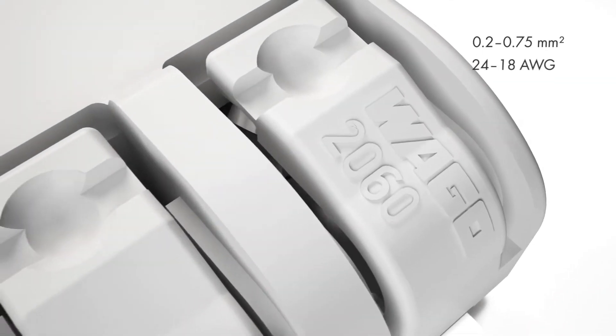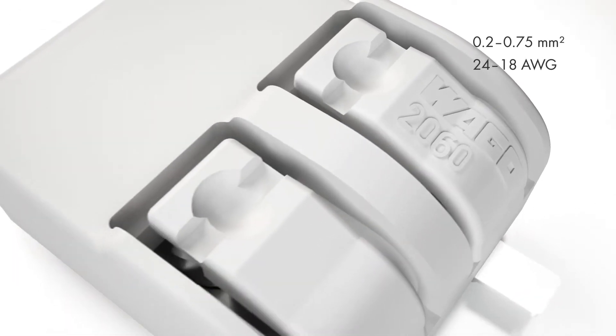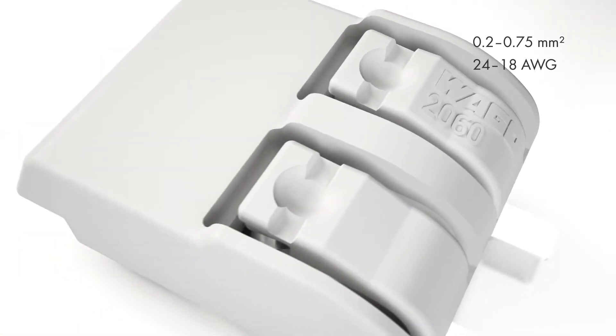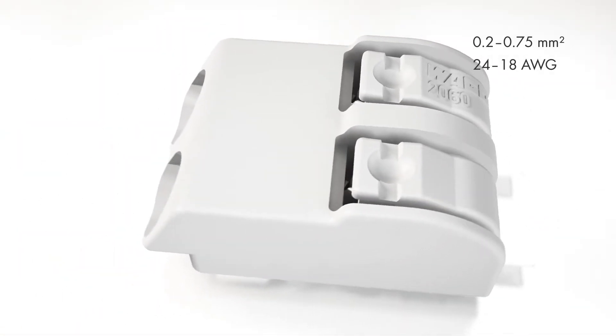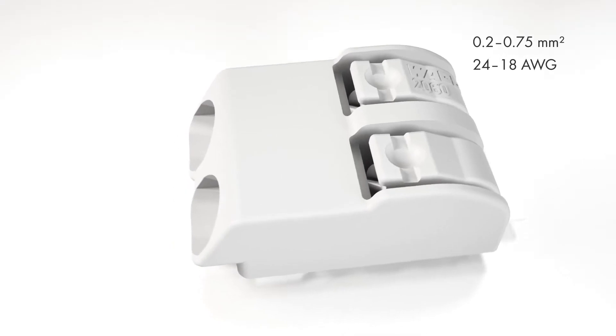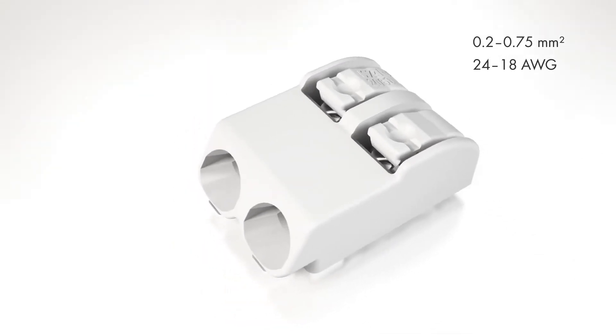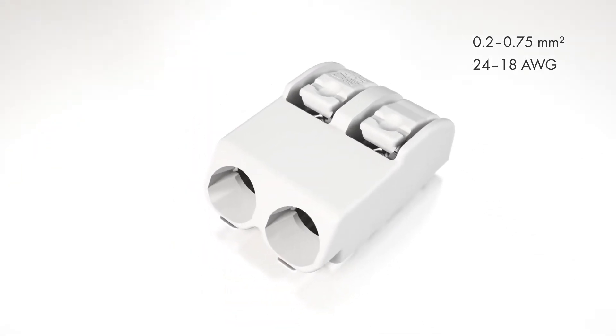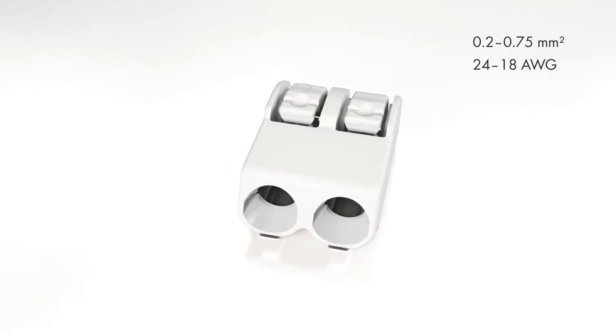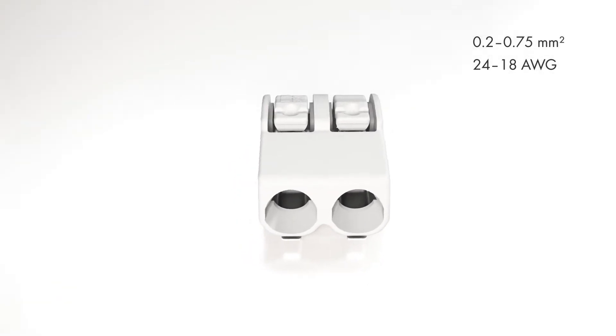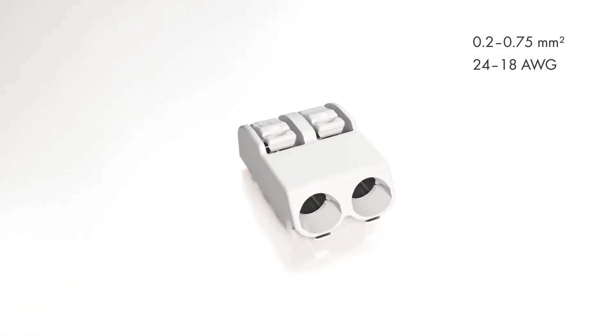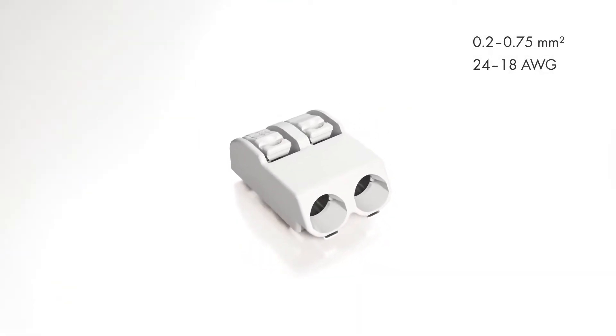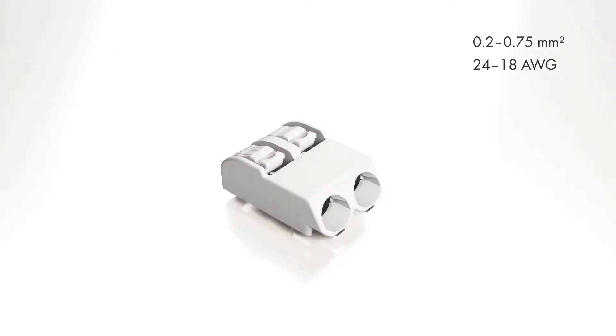They provide easy push-button terminations for solid and fine stranded conductors ranging from 24 to 18 AWG or 0.2 to 0.75 square millimeters. Just 4.5 millimeters high, Wago's 2060 series can readily serve diverse applications.